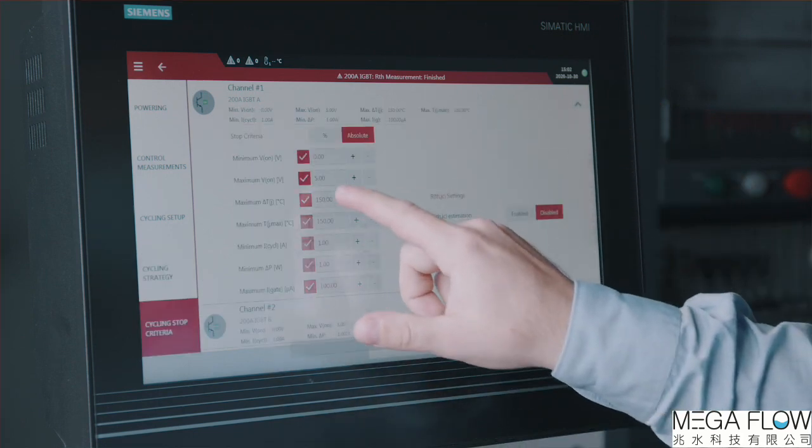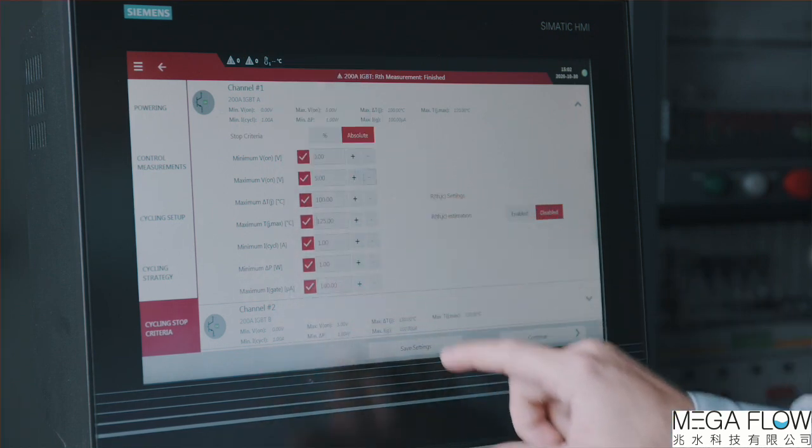Finally, the cycling stop criteria needs to be defined. The system monitors several parameters in each cycle, and if they exceed a certain threshold, the cycling is stopped automatically. Once the power cycling started, it will run automatically for days, weeks, or months, until the set maximum cycle number or another cycling stop criteria is reached.